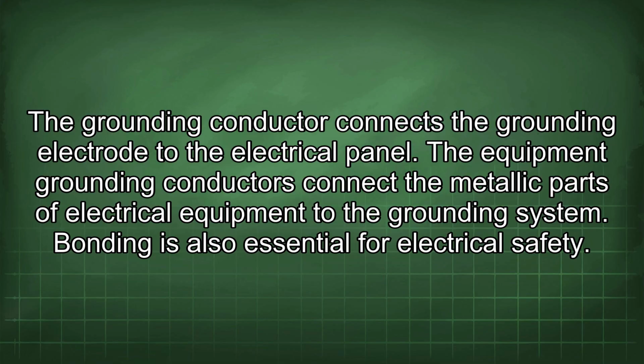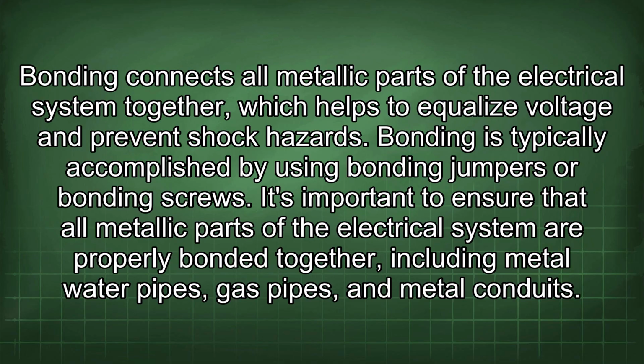Bonding is also essential for electrical safety. Bonding connects all metallic parts of the electrical system together, which helps to equalize voltage and prevent shock hazards. Bonding is typically accomplished by using bonding jumpers or bonding screws. It's important to ensure that all metallic parts of the electrical system are properly bonded together, including metal water pipes, gas pipes, and metal conduits.